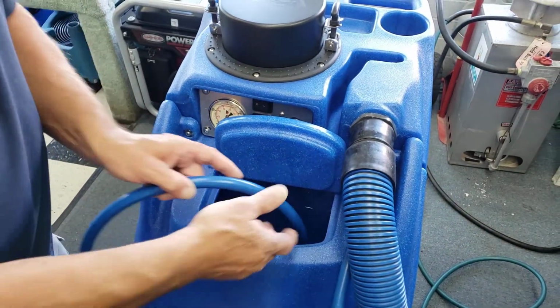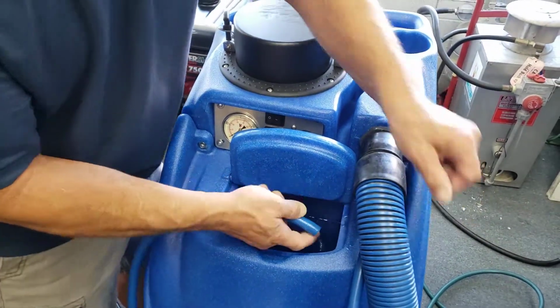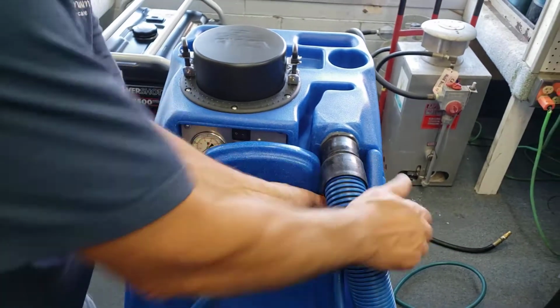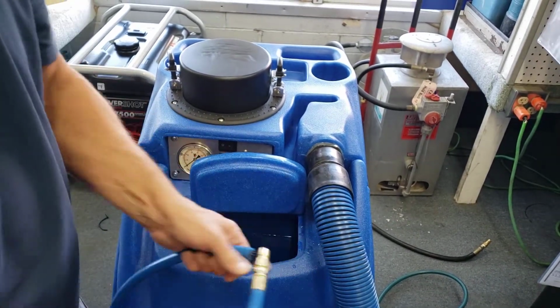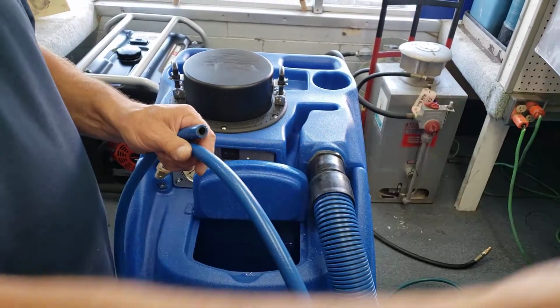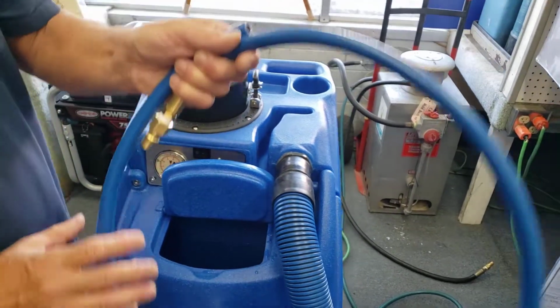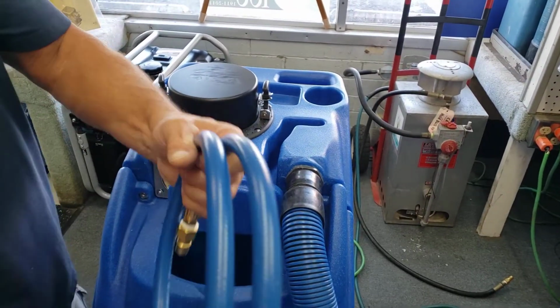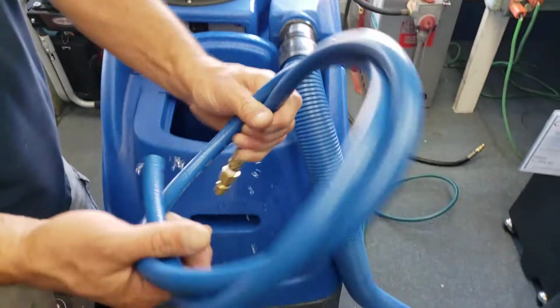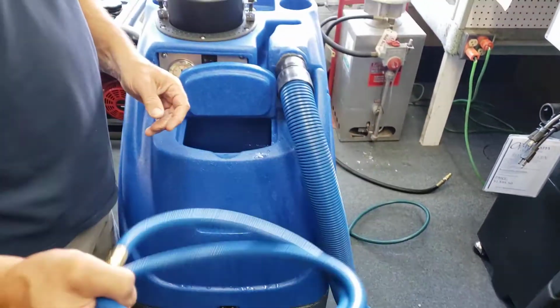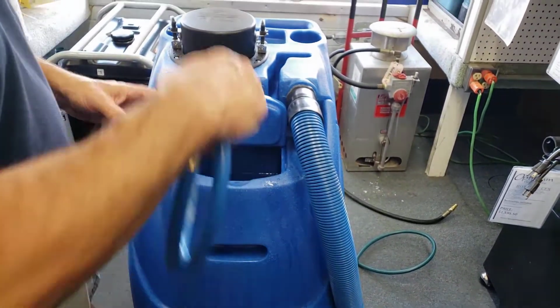You don't have to do this all the time. If you run out of water though, and you run it long enough, it will start to ingest air, and it can't clear the air just hooking it up to the wand. You need to use this to get the air bubbles out. Anytime you have a pump problem, the very first thing you need to do is hook up your bleeder hose and make sure you've gotten all the air out.